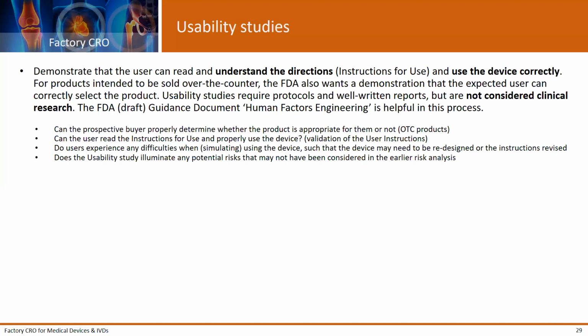Can the prospective buyer properly determine whether the product is appropriate for them or not, for example in terms of over-the-counter products? Can the user read instructions for use and properly use or deploy the device? Do users experience difficulties when using the device, though most of the time it's simulated use? And does the usability study illuminate any potential risks that have not been considered in the earlier risk analysis?